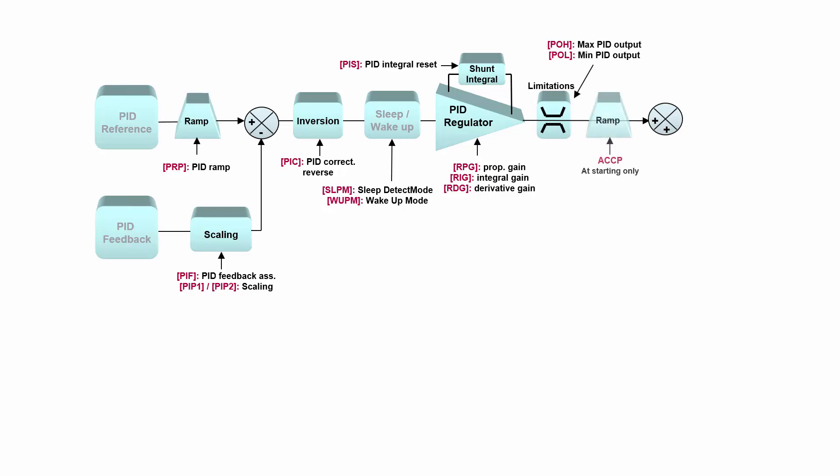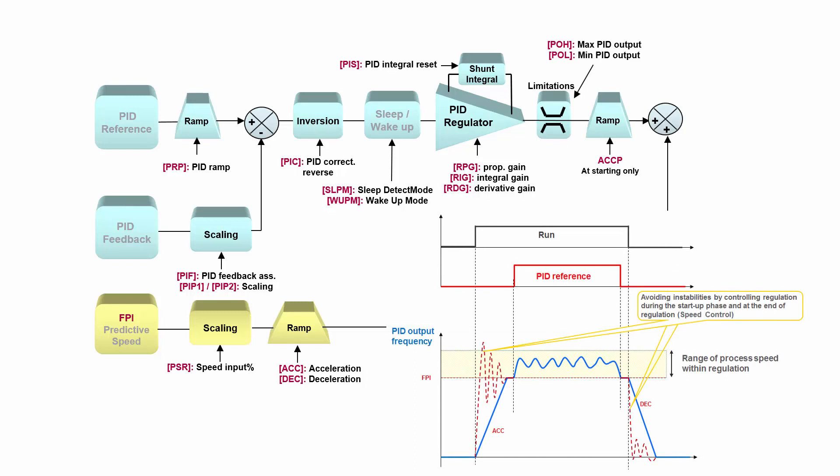Now the summing point is for predictive speed, which we can scale and ramp. Why do we use this predictive speed? We use it to avoid certain instabilities in our system, especially if we have a certain speed range where we can regulate. In between, we don't need PID regulator to work, but just ramp up and ramp down from this range.